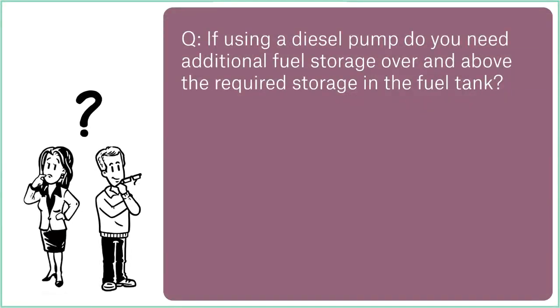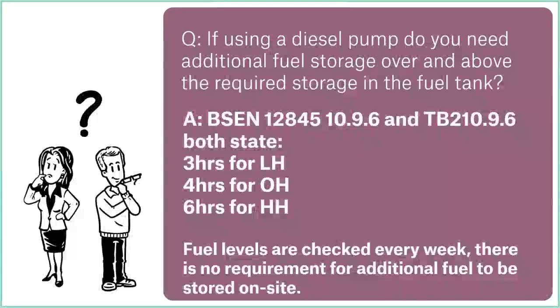So both BS EN 12845 and TB210 give a time. They don't give a quantity of fuel, because that depends on the actual engine itself. How thirsty the engine is will depend on how much fuel is required. So they haven't given a figure in litres, they've given a figure in time. For light hazard, we need 3 hours of fuel. Ordinary hazard, we need 4 hours of fuel, and for high hazard, we need 6 hours of fuel.